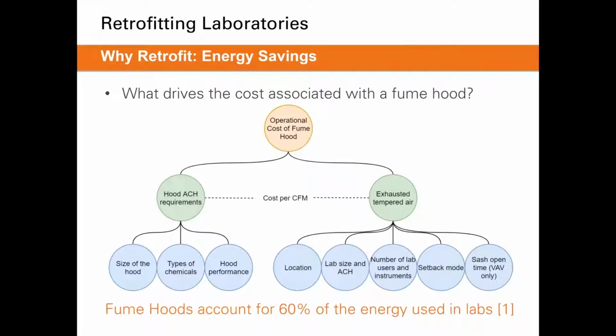So I put together this diagram here to show you kind of what drives the cost of operating a fume hood. And I'm focusing on the fume hood portion of a lab space because of this number at the bottom here. Fume hoods account for 60% of the energy used in labs. So they do account for the majority of the energy consumption. And if one of your goals is energy savings for a lab, then you will want to focus on fume hoods as that will be a huge portion of that opportunity. So a couple things drive the operational cost of a fume hood. First would be the ventilation requirements of the hood itself. And then, as I mentioned before, the amount of exhausted tempered air that goes through those hoods, that energy is also directly related to that hood.